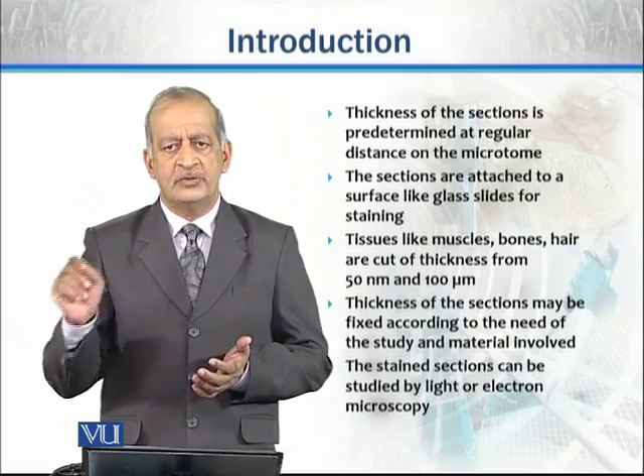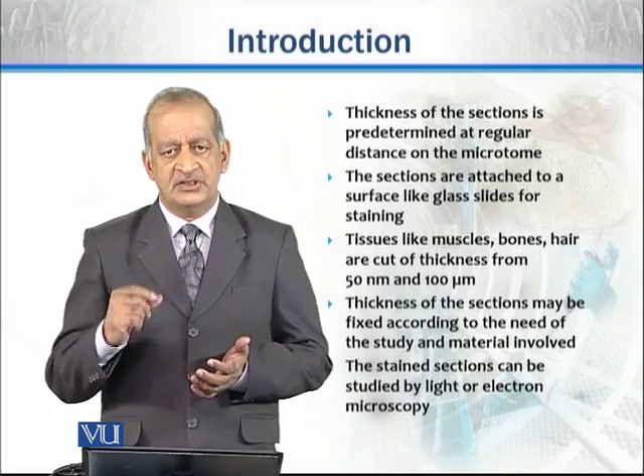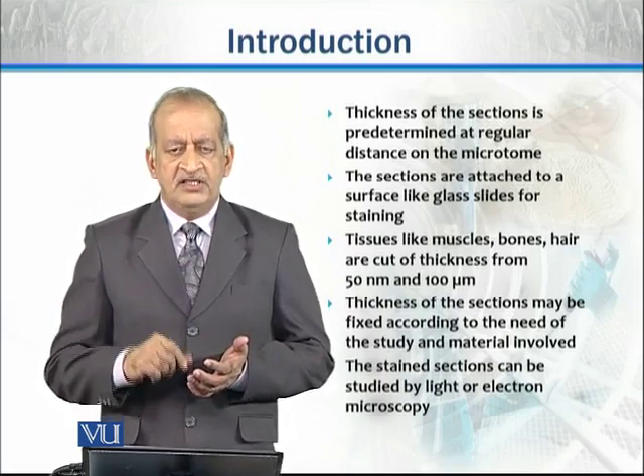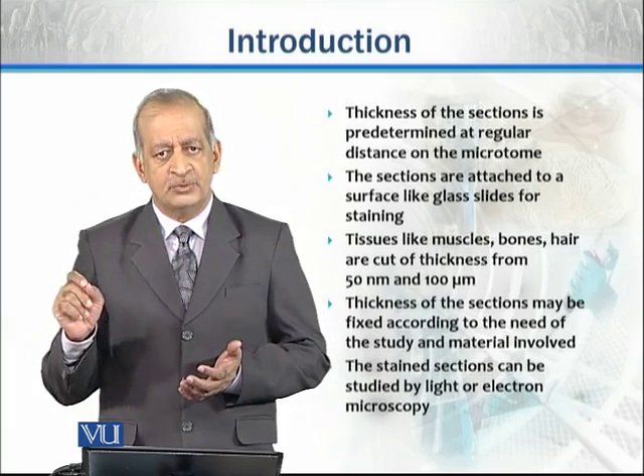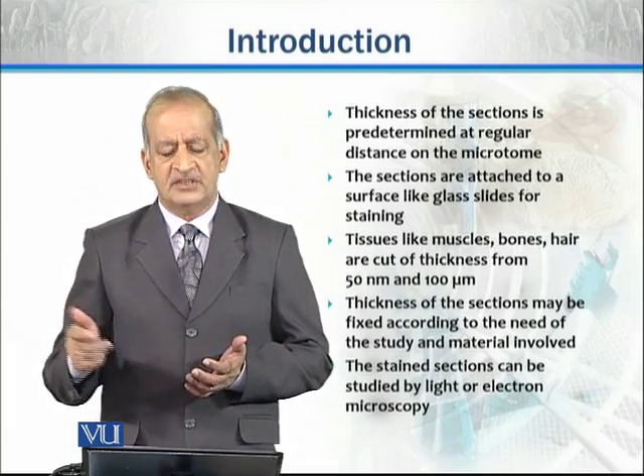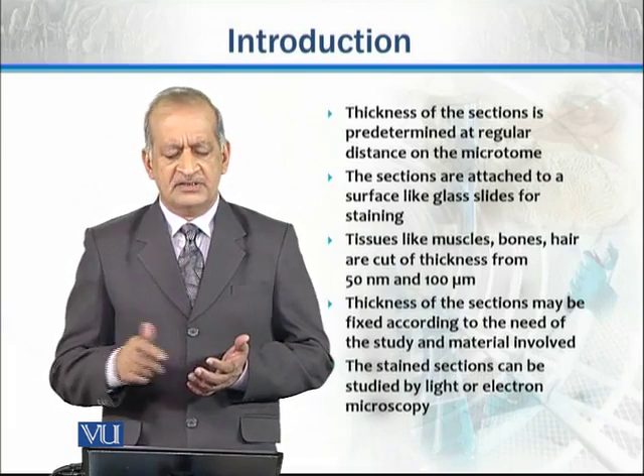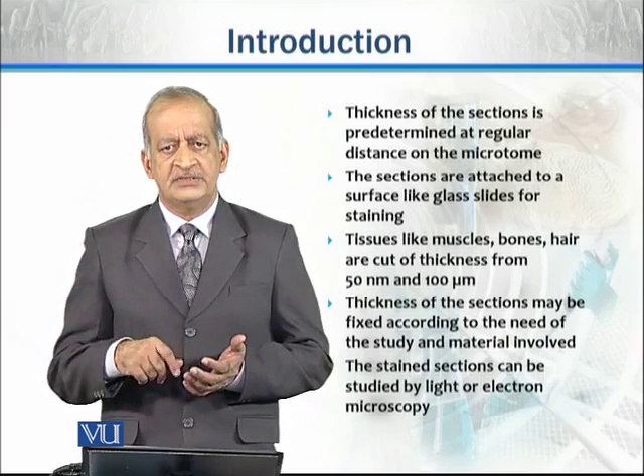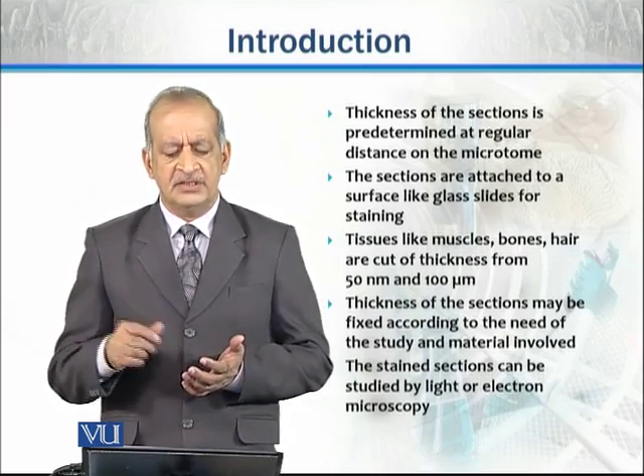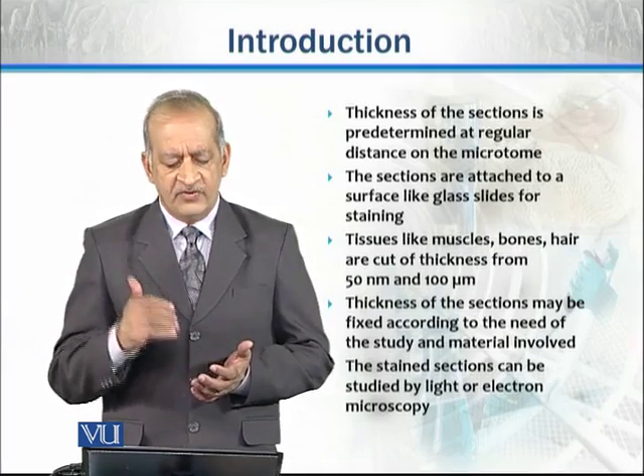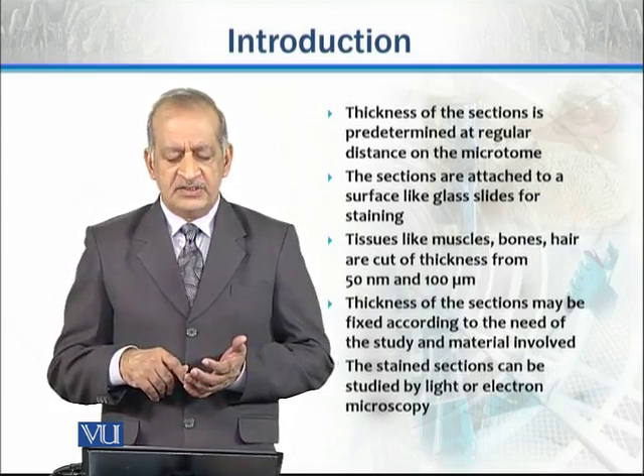We can fix the desired thickness on the microtome, and when we operate it, we get sections of that particular thickness. These sections are attached to a supporting surface such as a glass slide for staining. Tissues like muscle, liver, and other animal and plant tissues, including bones and hairs, may be cut from 50 nanometers to 100 micrometers in thickness.